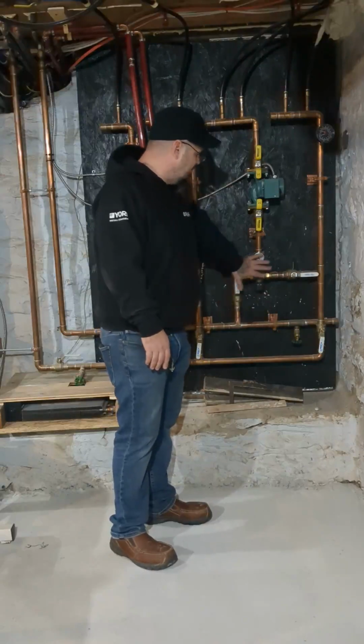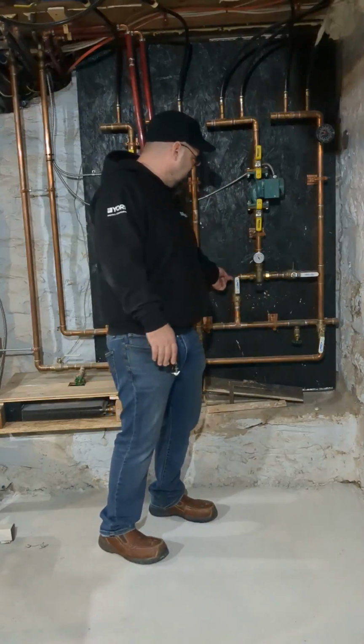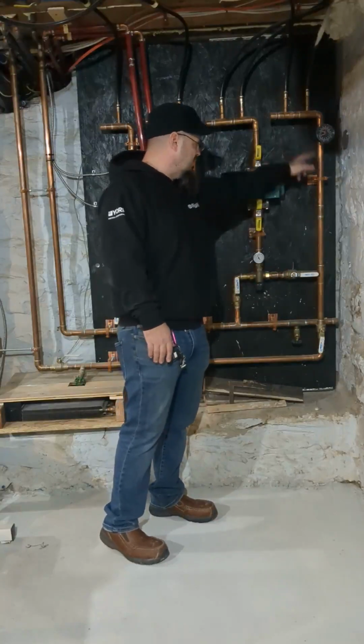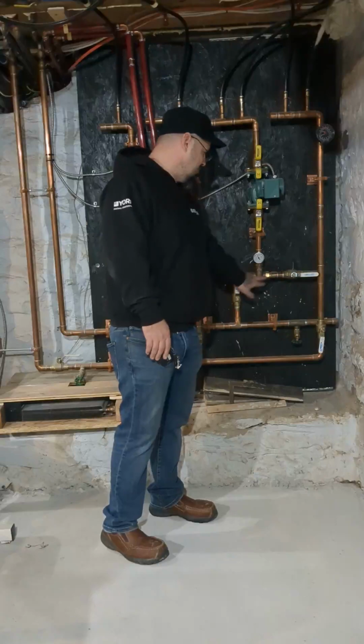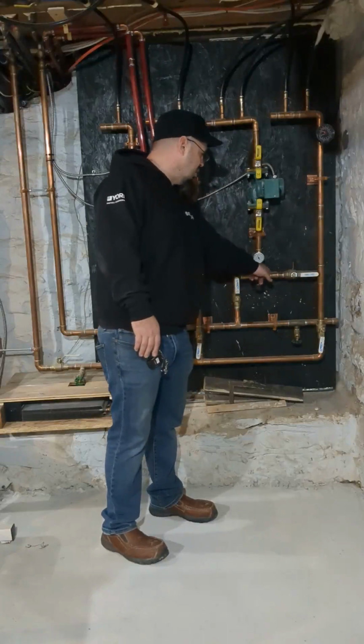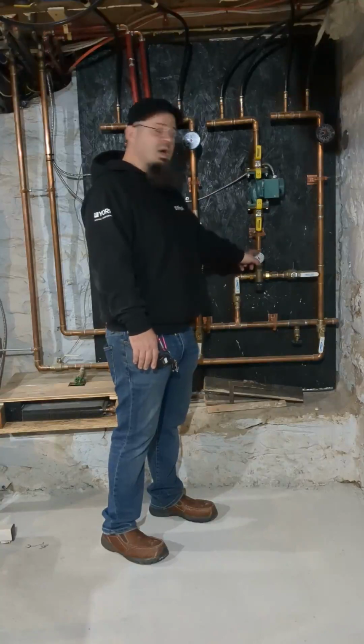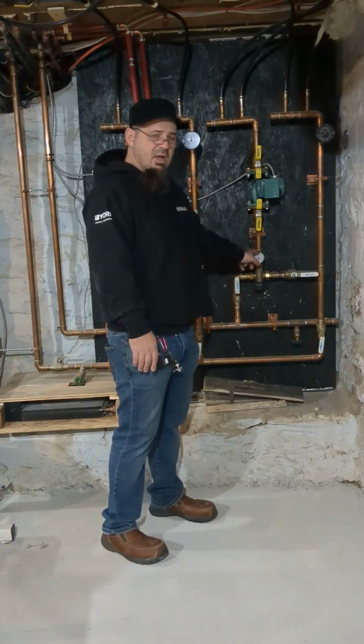This piping setup, you should be able to see something like this. Supply water coming in, return water coming in to bring this temperature back down. That's what this is all about. I'm mixing a little bit, mixing valve, right? I'm mixing a little bit of return water in with my supply water temperature so that I can ultimately end up with the right outgoing supply that I'm looking for.